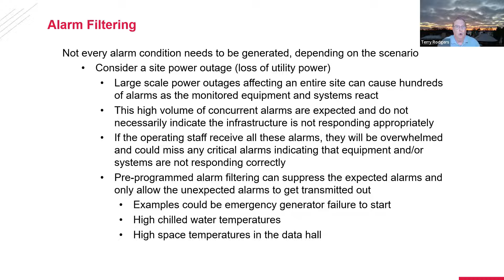And the next thing you know, you've got a cascade of hundreds, if not thousands, of alarms that come rolling through, almost all of which are normal. It's what you would expect to occur with a power outage. What you want to do is filter out the normal stuff and find those that are saying something that was expected did not occur. A chiller that failed to restart, a generator breaker that failed to close, so you're not getting power. And you don't want the staff to miss that or to have to go hunt and peck for it. So you want that to rise to the top of the alarm list, and you want to otherwise suppress the normal stuff.